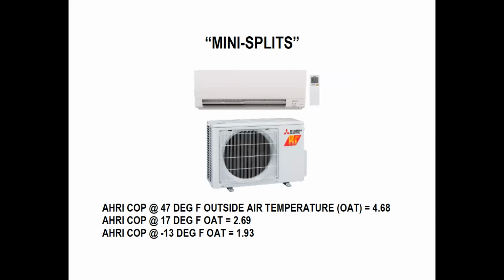Okay. So AHRI is the Air Conditioning, Heating, Refrigeration Institute. It's an organization that takes people's heat pumps and runs them through the different temperatures outside. And it says, yep, at this temperature you're going to have this performance, at 17 degrees and 47 degrees, the two places where they talk about that. They measure it, and at those two temperatures they have different coefficients of performance. So you can see at 47 degrees, I'm getting a whole lot of energy out of that air delivered into the space at efficient rates. At 17, it's less. And then at minus 13, it's that.